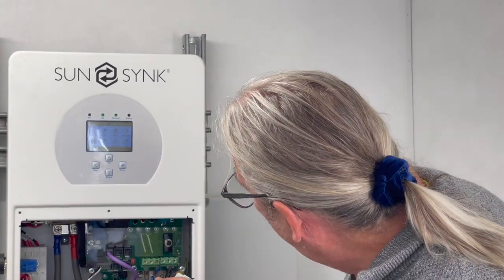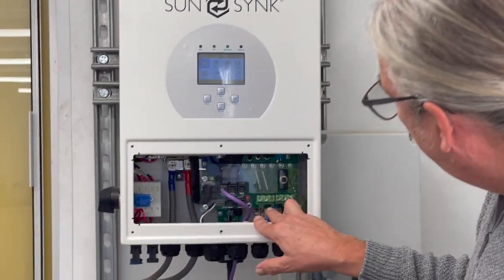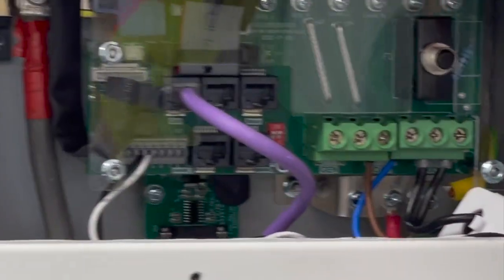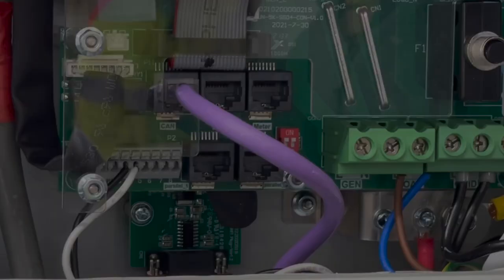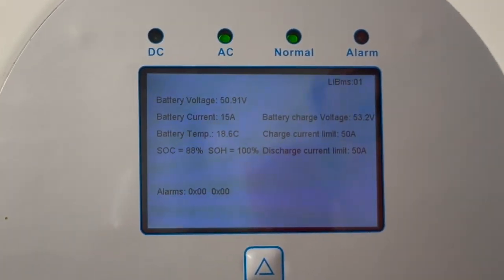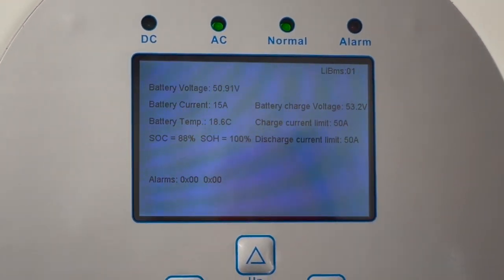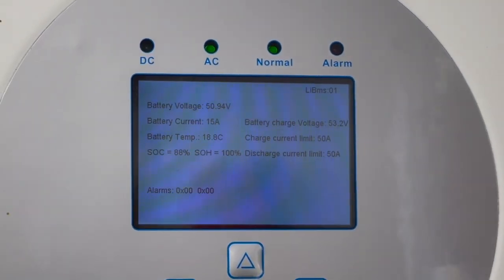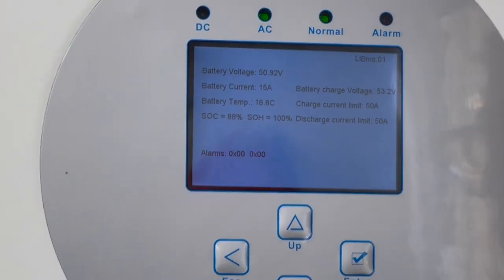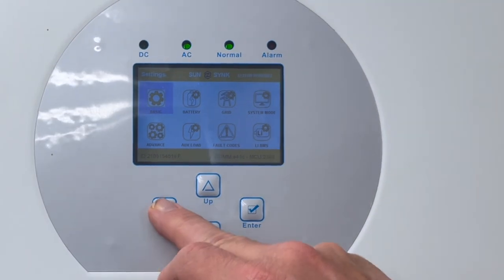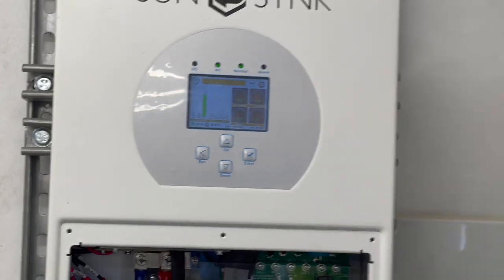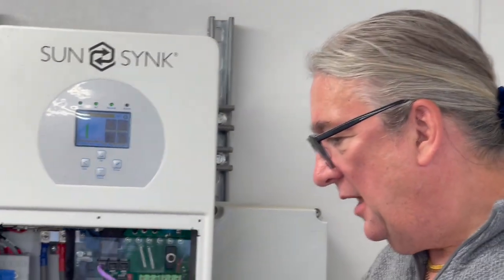And you see from the board here, they haven't used the gen inputs - they're just simply using the grid. We've got good communication going to the battery here, you can see there's good comms. In fact, you see they've actually limited to 50 to 60 amp on the BMS. I've gone slightly higher, which is fine, because the battery BMS will override anyway - they'll allow any tolerance. So based on those settings, they should be fine.